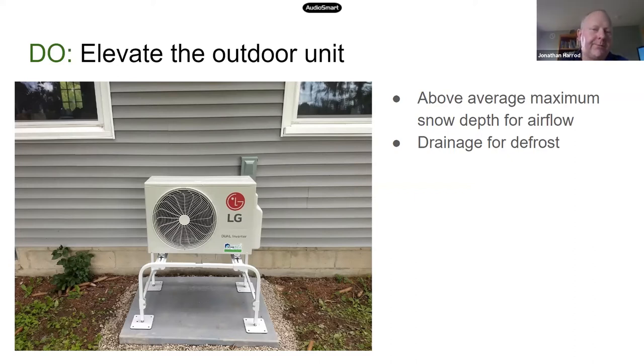But also really important is that we need to have free drainage under the unit. Because these are extracting heat from the outdoor air, they're cooling the air that flows through them in the wintertime, and so frost forms on the coils. And in cold weather, a couple times an hour, they will have to switch into defrost mode, and that frost that forms on the coils gets melted off and drips away.